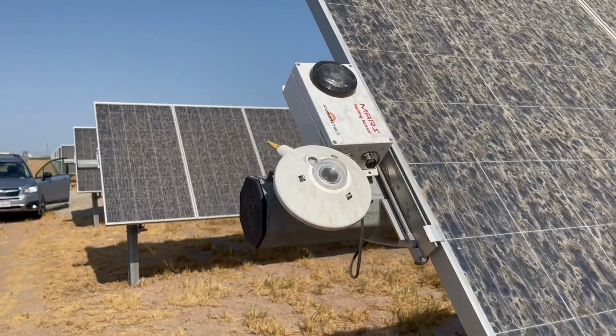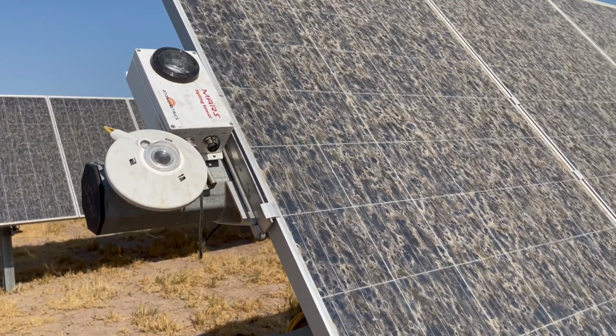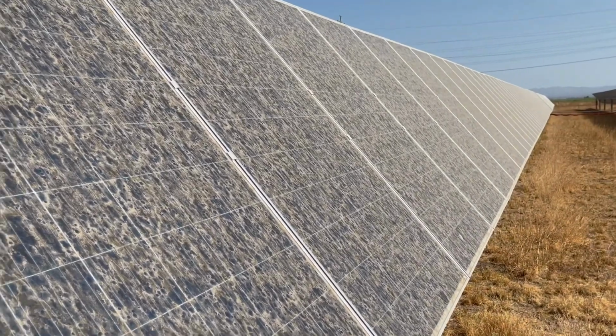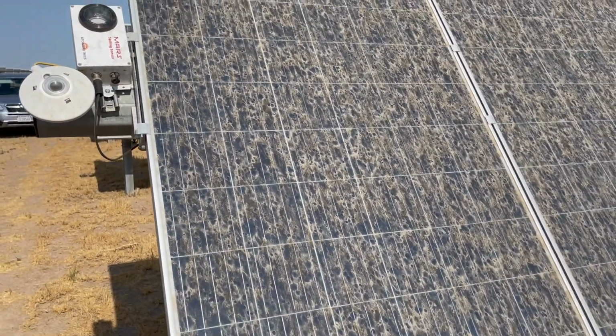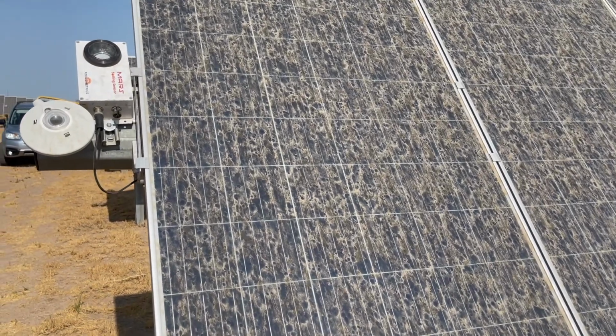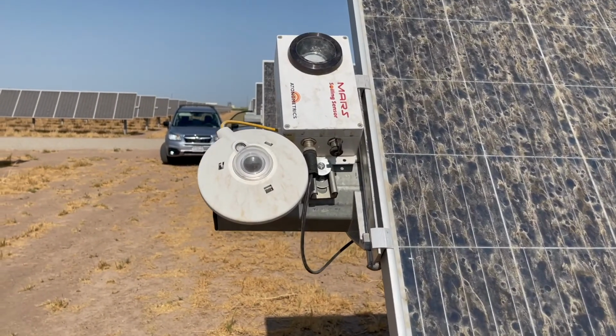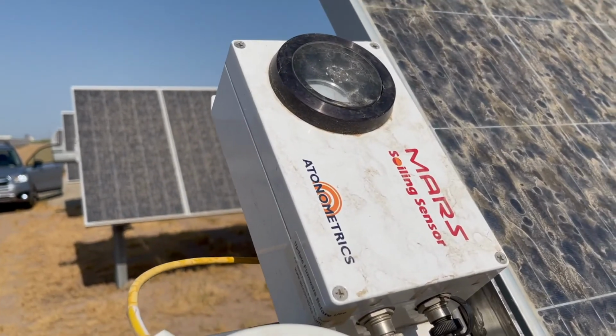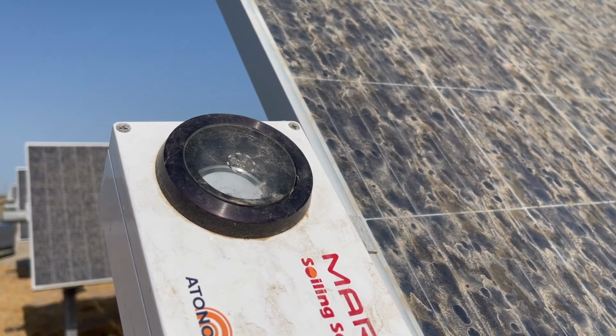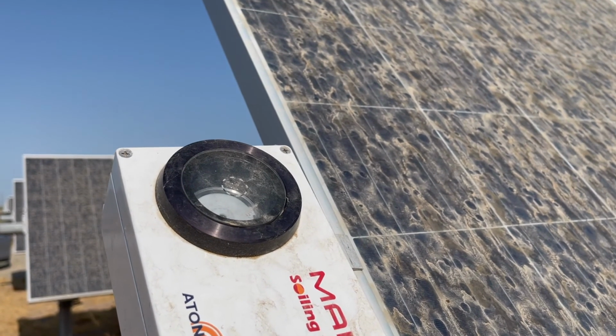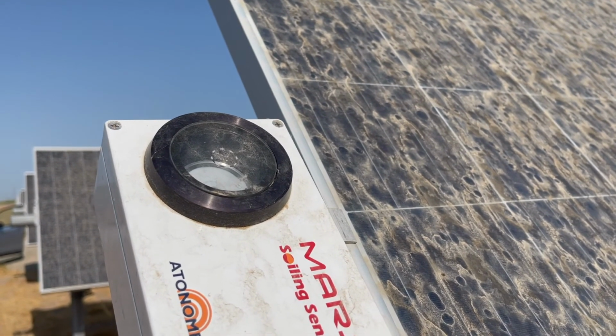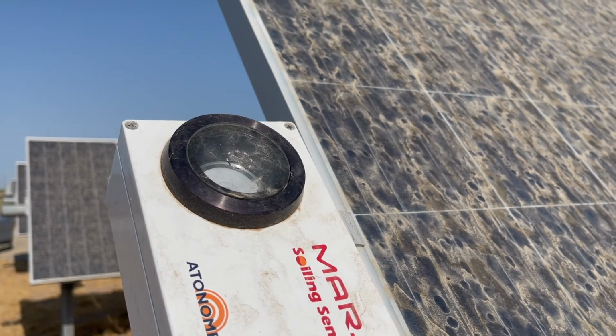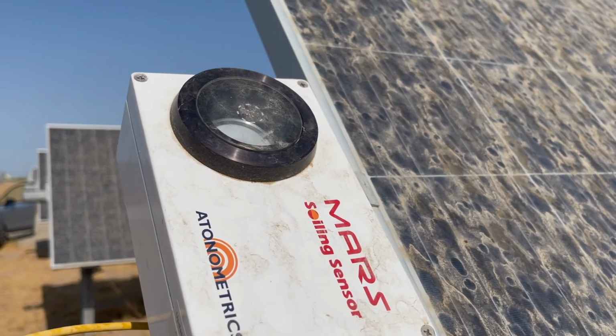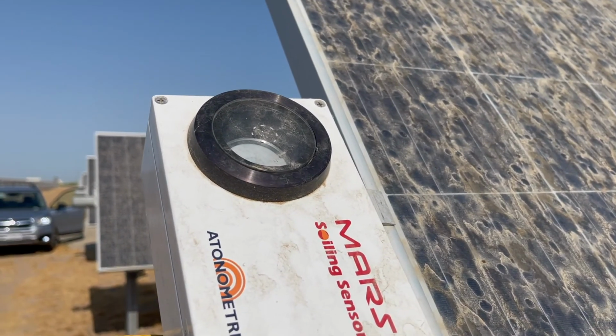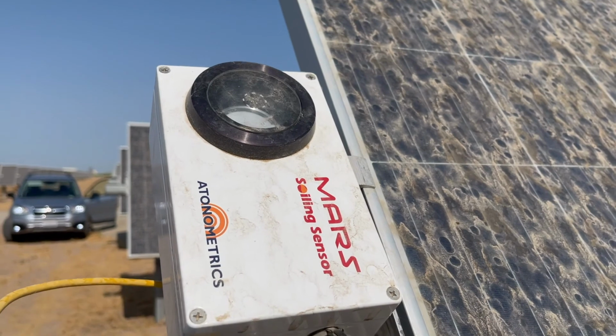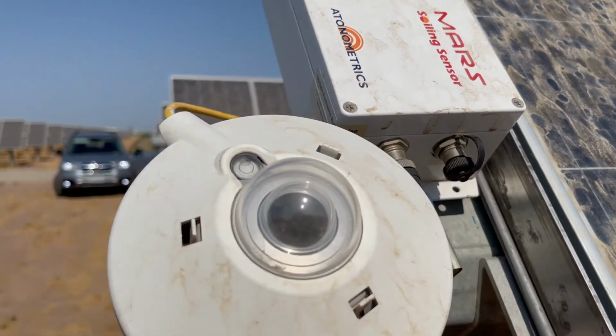So here we go. This is a soiling inspection. You can see all the modules are about the same. Somehow it rained a little bit, just a little bit. If it would have rained about 3 times as much, they'd be clean basically. And so here's our soiling sensor. The dirt on that lens looks just like the modules. And without getting out the Excel spreadsheet, it looks like my tests are about 19% soiled. And I think that's what the sensor told Angelo yesterday. So lo and behold, it's accurate once again.